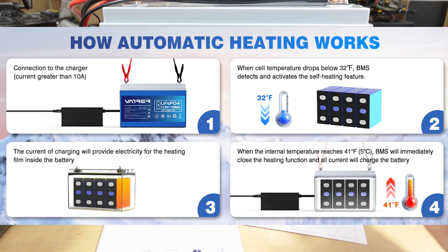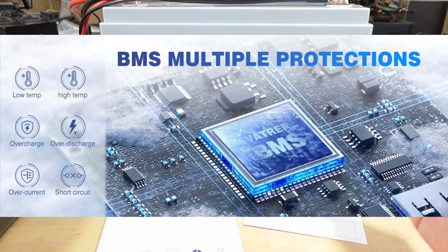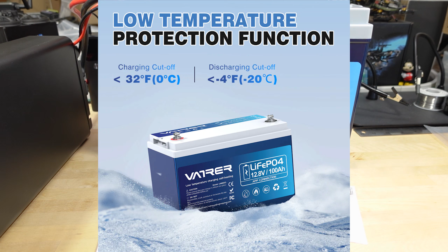So there's a lot of protections in place. This one has it, just like a lot of other batteries. Low temperature protection is very important for this chemistry, and it will not allow the battery to charge if the temperature falls below 32 degrees. It also has a discharge cutoff at negative 4 degrees Fahrenheit, so it will allow the battery to discharge below 32 degrees Fahrenheit all the way down to negative 4 degrees, which is kind of amazing. But charging the battery at that temperature is actually really dangerous. Apparently discharging it below freezing still works, but it's not recommended.